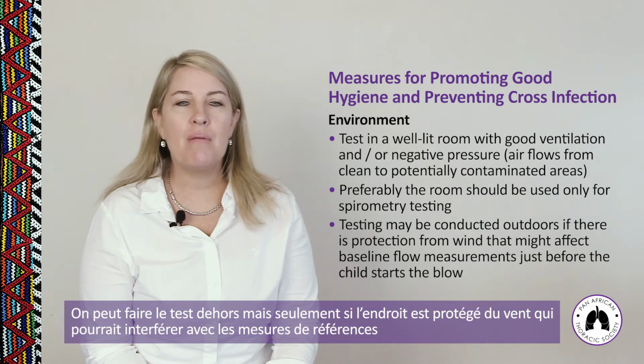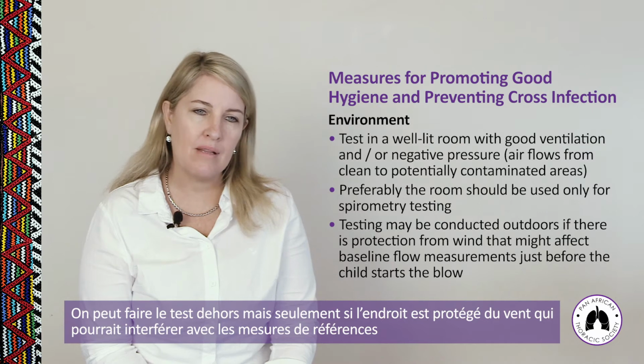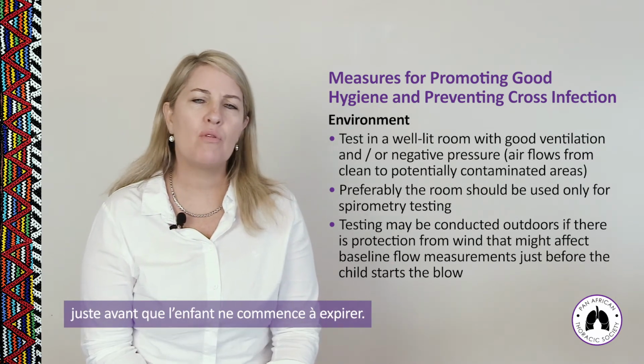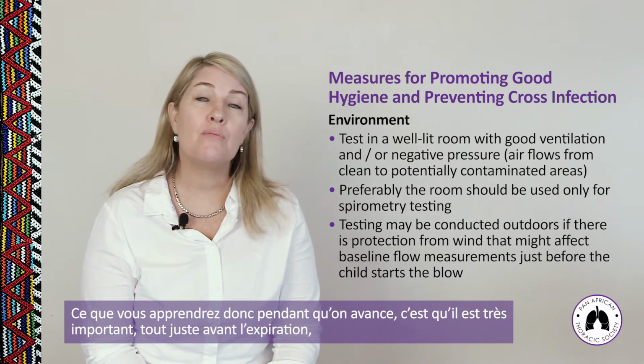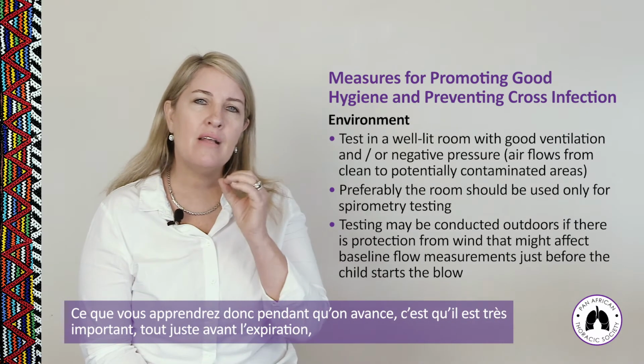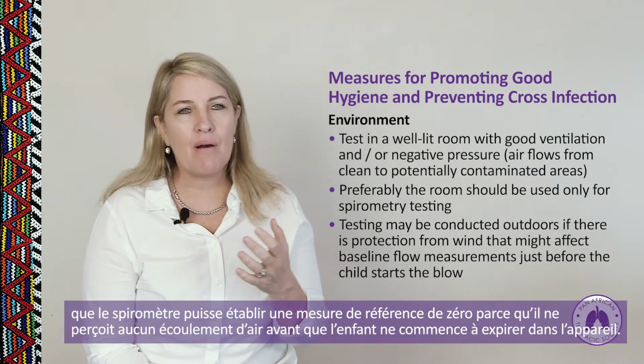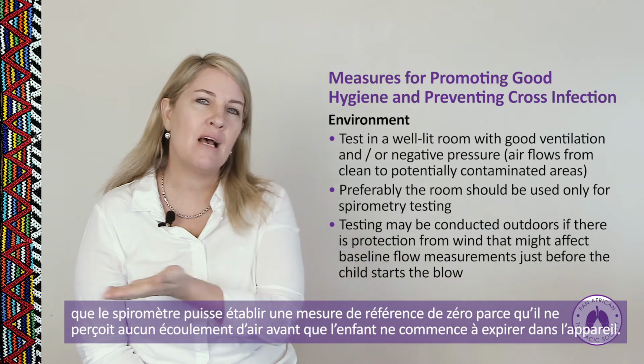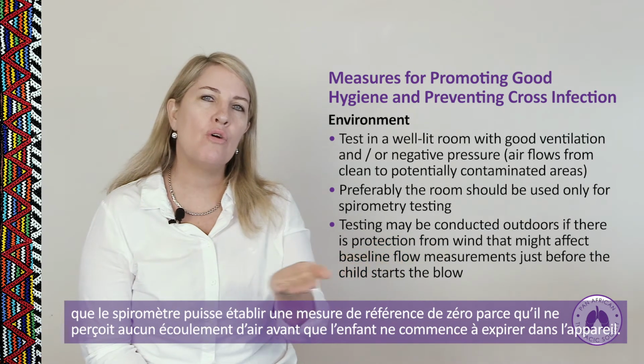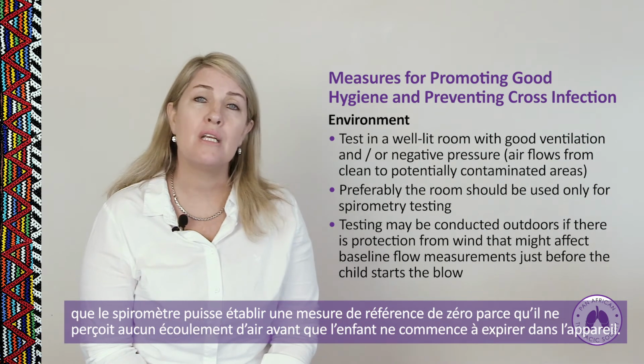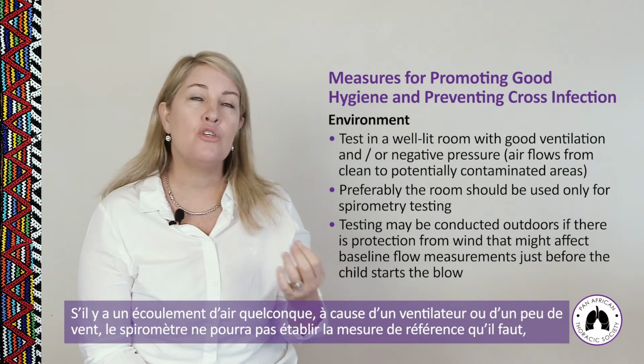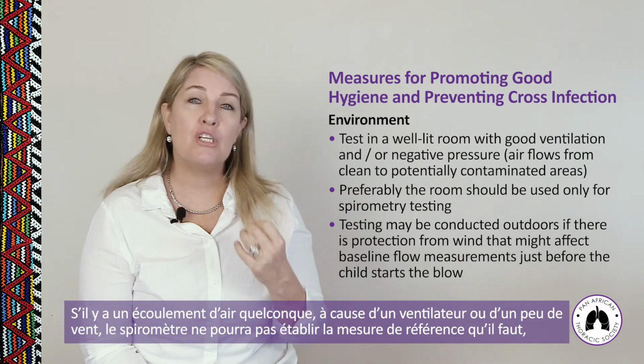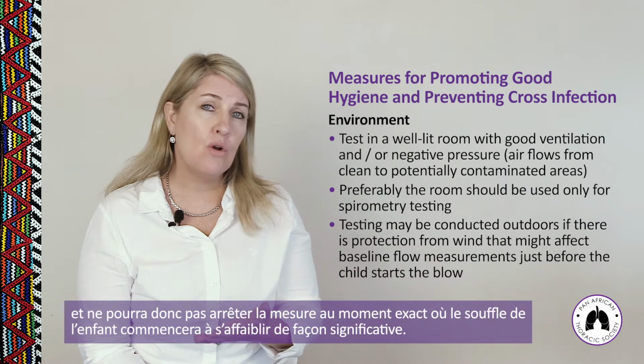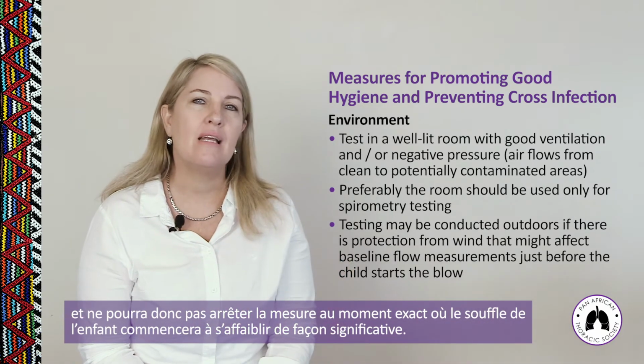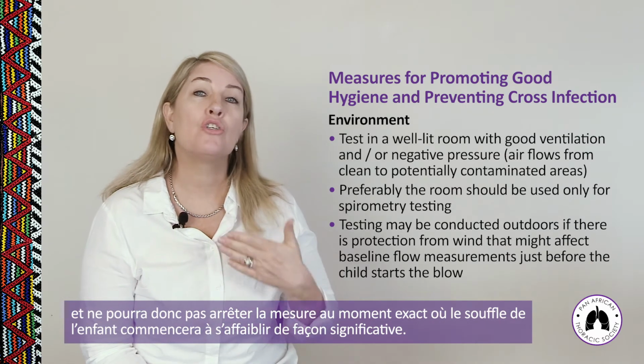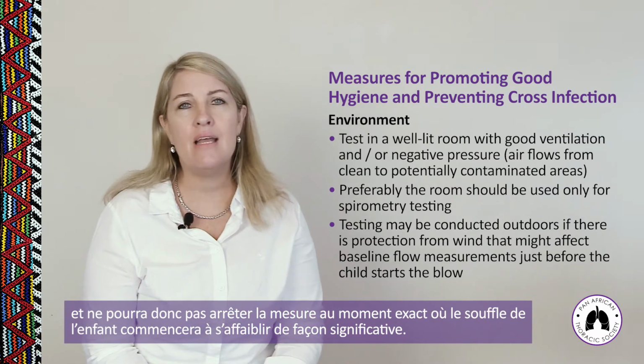Testing may sometimes be conducted outdoors if there is protection from wind that might affect baseline flow measurements just before the child starts to blow. It's very important that in those few moments before the blow, the spirometer can set a zero baseline for flow—meaning it measures no air flow before the child begins blowing. If there is airflow due to a fan or wind, the machine won't read the baseline properly, and it won't cut off the test correctly when the patient's flow slows down to indicate the end of the test.